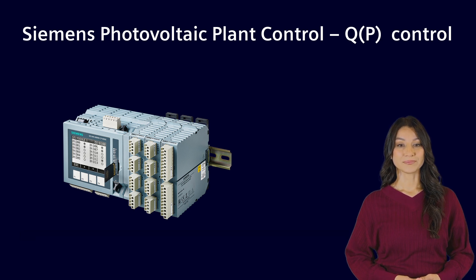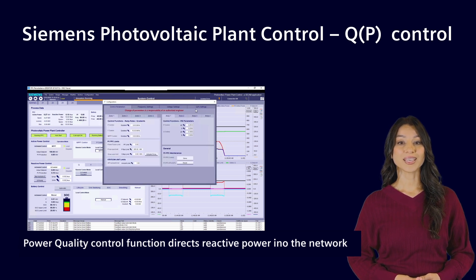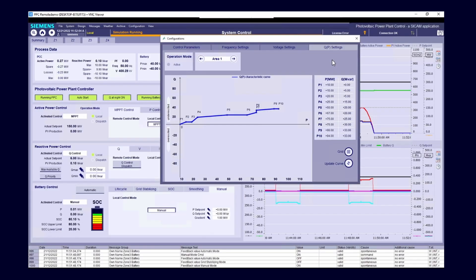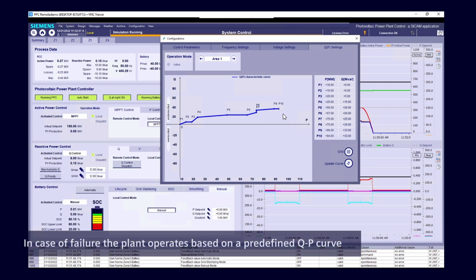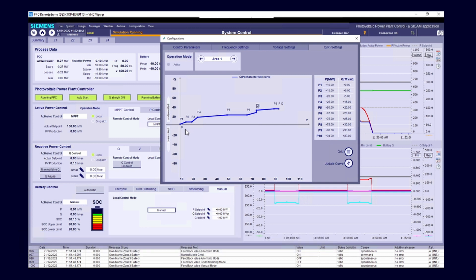A power quality control function can direct reactive power into the network based on the current active power output at the point of common coupling. The network operator can adjust set points as required. In case of telecontrol link failure, your plant operates based on a predefined QP characteristic curve.